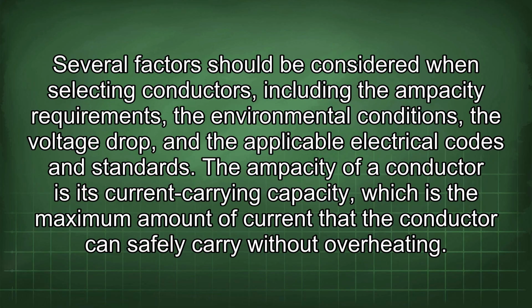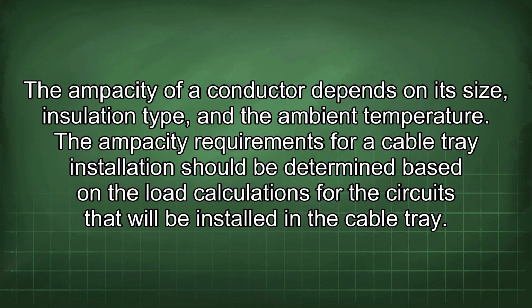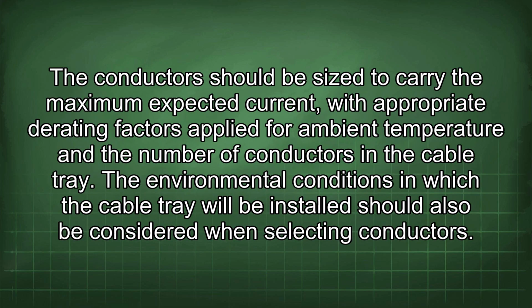drop, and the applicable electrical codes and standards. The ampacity of a conductor is its current carrying capacity, which is the maximum amount of current that the conductor can safely carry without overheating. The ampacity of a conductor depends on its size, insulation type, and the ambient temperature. The ampacity requirements for a cable tray installation should be determined based on the load calculations for the circuits that will be installed in the cable tray. The conductors should be sized to carry the maximum expected current, with appropriate derating factors applied for ambient temperature and the number of conductors in the cable tray.